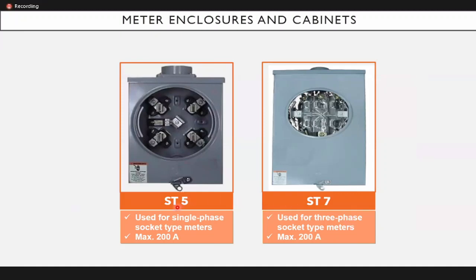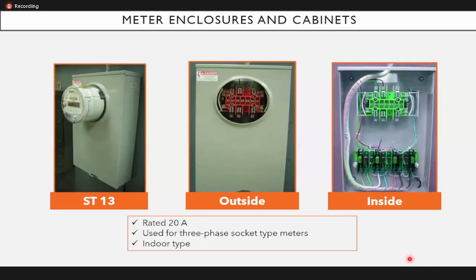For the socket type 5 terminals and socket type 7 terminals, these are used for single phase socket type meters. And this one, ST7, is used for socket type 3-phase meters. Both of them have a maximum of 200 amperes. This is among the old type already. And ST13 has a rating of 20 amps, and it is used also for 3-phase socket type meters indoor.